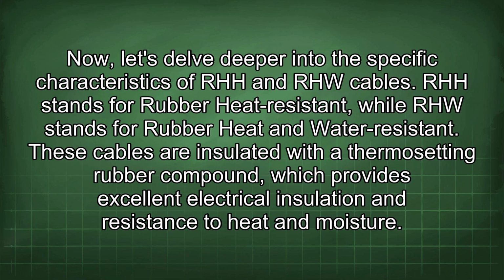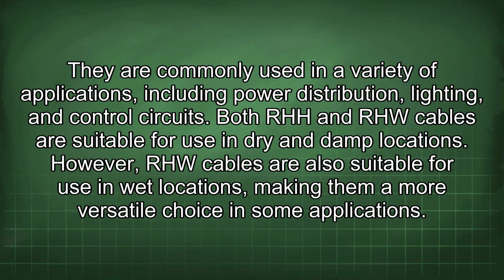Now let's delve deeper into the specific characteristics of RHH and RHW cables. RHH stands for rubber heat resistant, while RHW stands for rubber heat and water resistant. These cables are insulated with a thermosetting rubber compound, which provides excellent electrical insulation and resistance to heat and moisture. They are commonly used in a variety of applications, including power distribution, lighting, and control circuits. Both RHH and RHW cables are suitable for use in dry and damp locations. However, RHW cables are also suitable for use in wet locations, making them a more versatile choice in some applications.